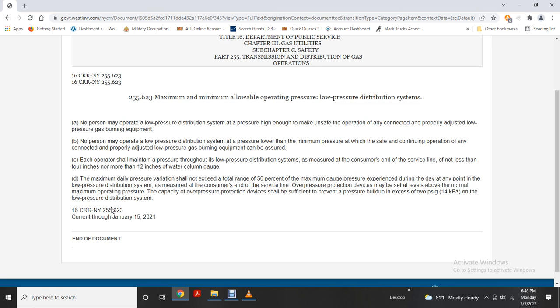Maximum daily pressure variations must not exceed a total range of 50% of the maximum pressure experienced during the day at any point within the low pressure distribution system, measured at the consumer end of the service line. Overpressure protection must be set at safe levels above normal maximum operation. The capacity of the overpressure protection device shall be sufficient to prevent pressure buildup in excess of 2 psi gauge on the low pressure distribution system.